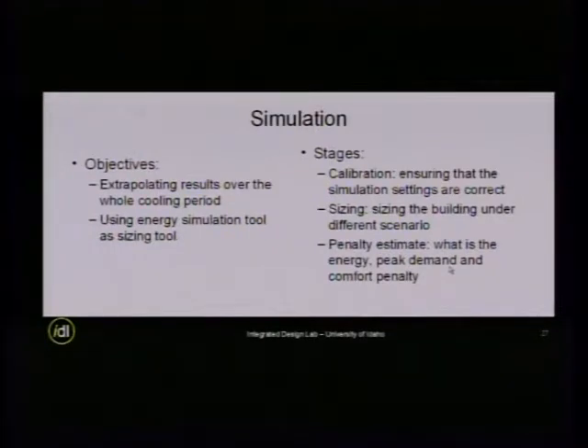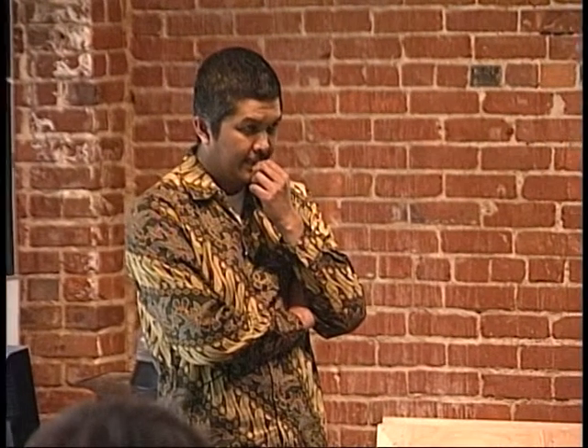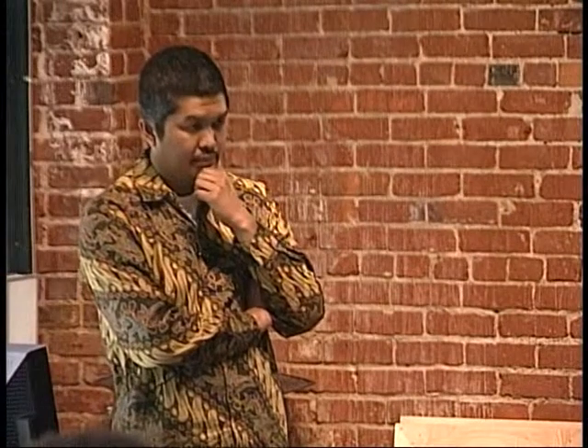Yes, any questions? Is there any indication of the cost consequences of excessive wear and maintenance on excessive cycling versus minimal cycling? Because you have an energy saving, but I could just see these RTUs just zipping out if they're excessively cycling. The question is whether there is a maintenance issue with the oversizing, the cycling, or the running constantly.